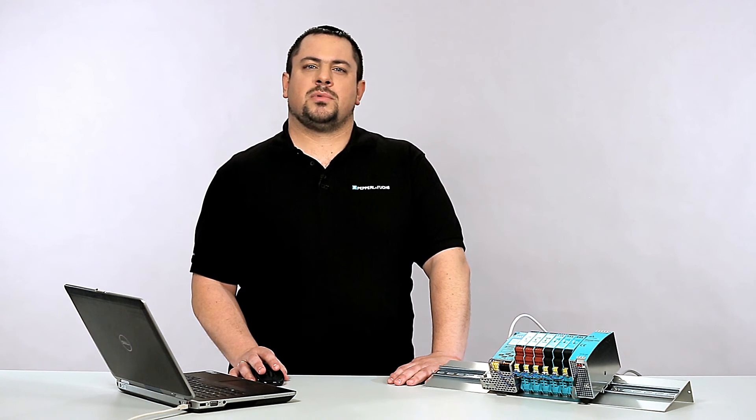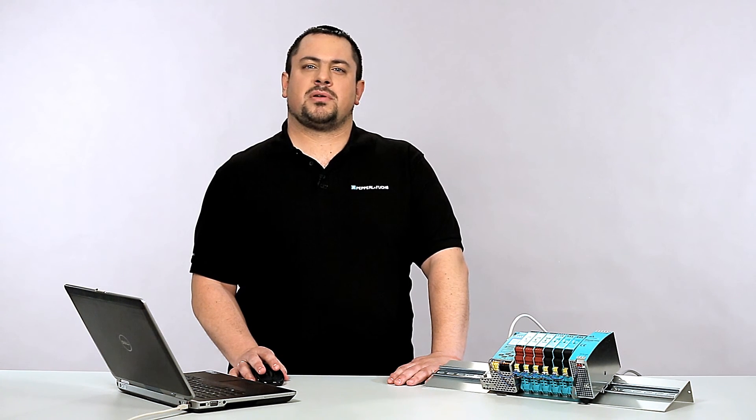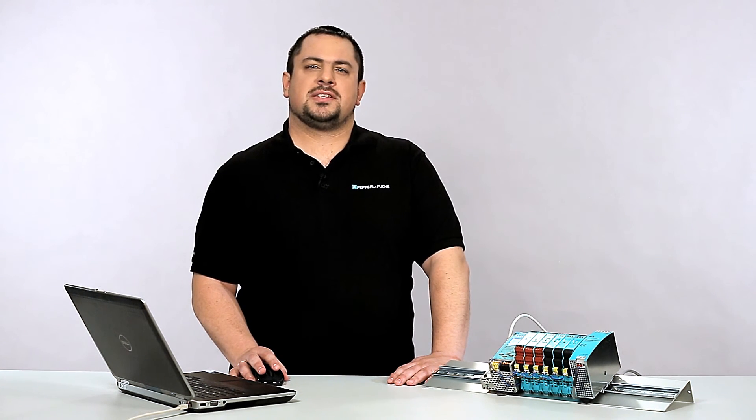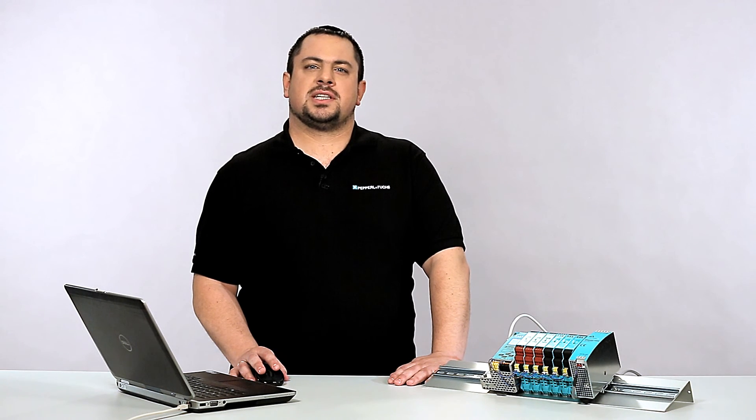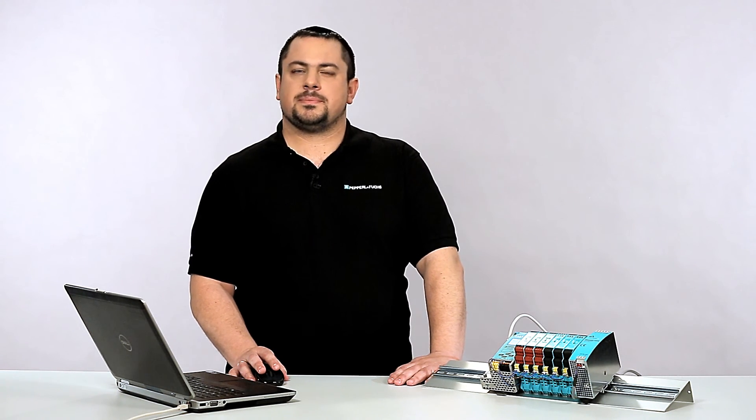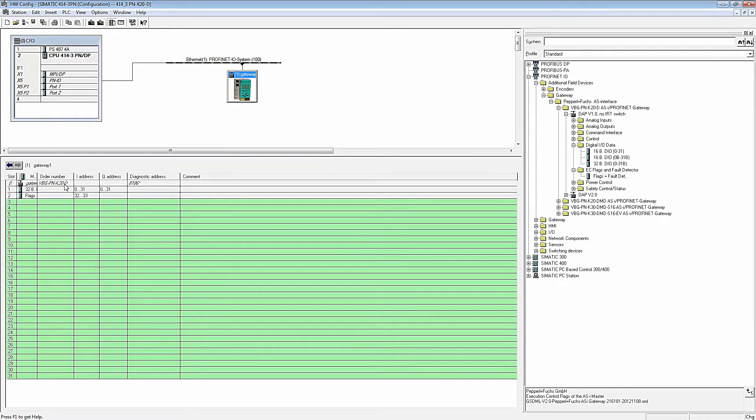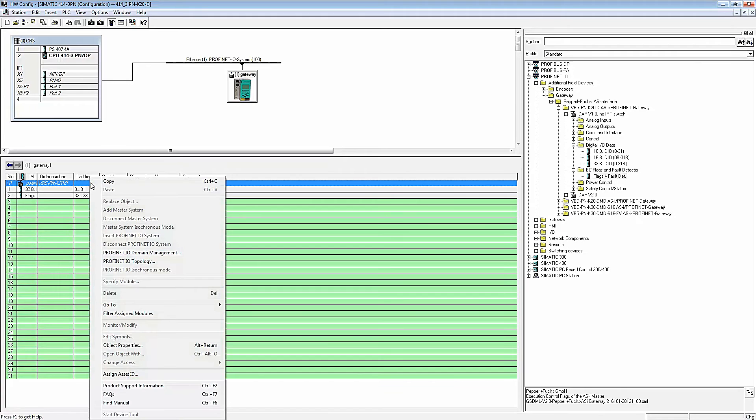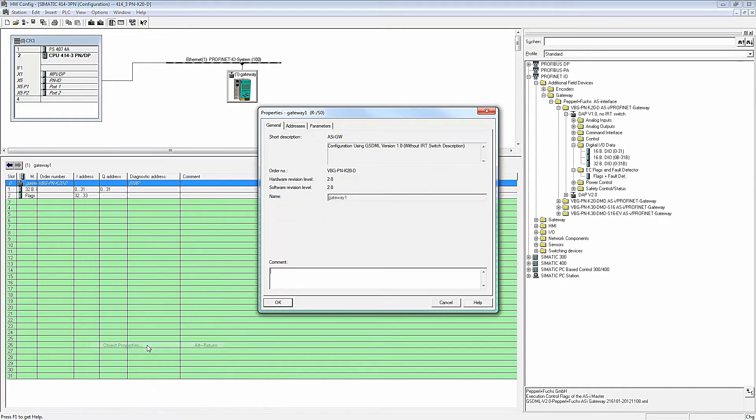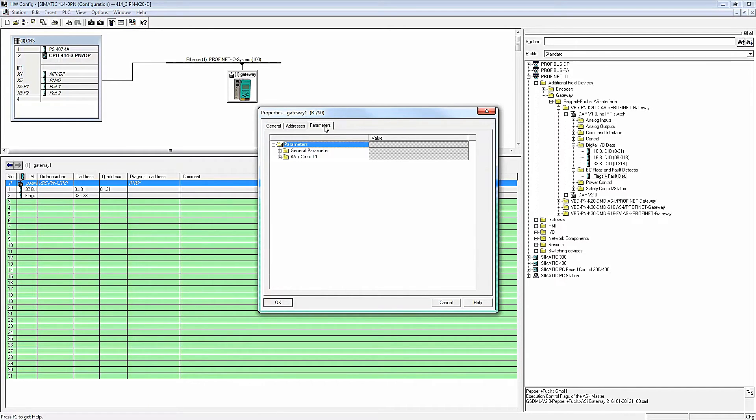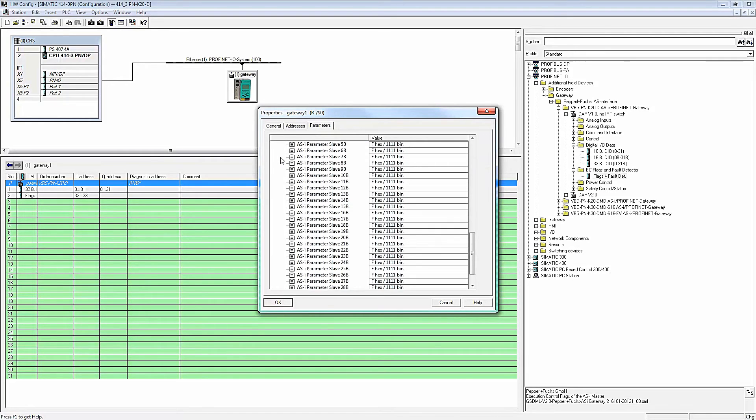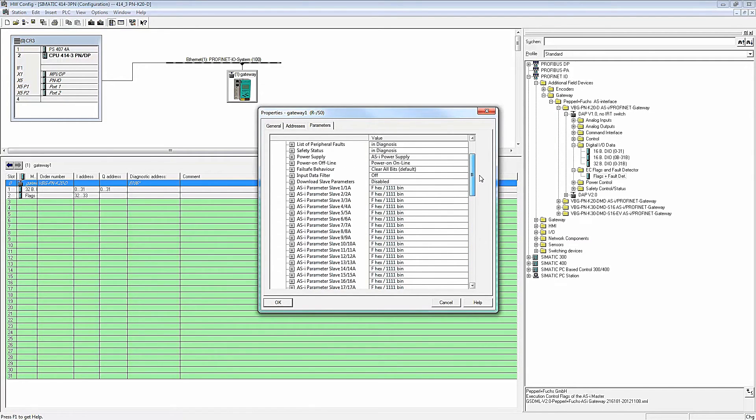If you want to set more device specific parameters, such as individual AS interface slave parameters, right click on the row of slot 0 and then click Object Properties. In the Parameters tab, you will find different settings for the individual slaves, but also for the scope of the diagnostic data of the master.